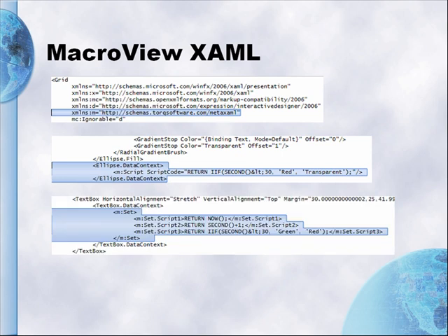And you can group within the XAML multiple scripts into one object. That's required because the data context property only takes one object. And in this scenario, you combine one property of a graphic to one script, another property to another script. The XAML is like a big tree of information. At the top level, you've got the screen, then you've got n objects, and each object can have n objects within it, and each object can have its own graphic properties like colour, position, size, etc. So that's the engine room of the XAML functionality.